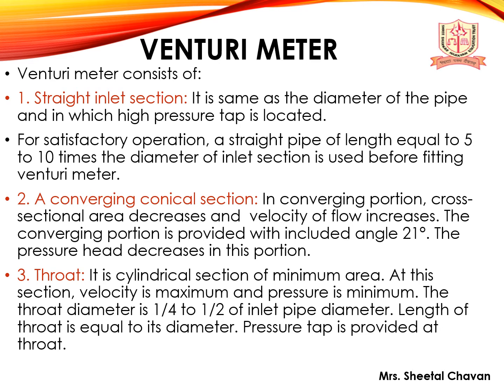The venturimeter consists of a straight inlet section with the same diameter as the pipe, where the high-pressure tap is located. A straight pipe length equal to 5 to 10 times the inlet diameter is required before fitting the venturimeter. In the converging conical section, the cross-sectional area decreases and velocity increases, with an included angle of 21 degrees, and pressure head decreases. The throat is the cylindrical section of minimum area, where velocity is maximum and pressure is minimum. The throat diameter is 1/4 to 1/2 of the inlet pipe diameter, with length equal to its diameter, and a pressure tap is provided there.